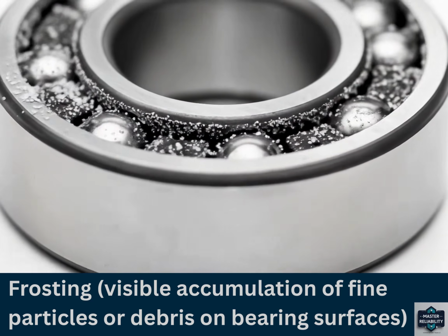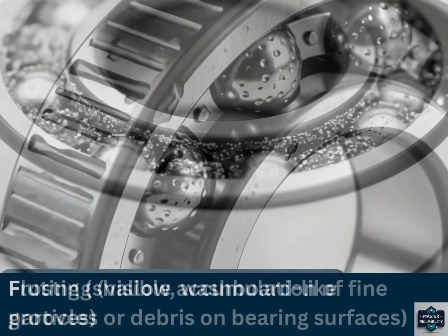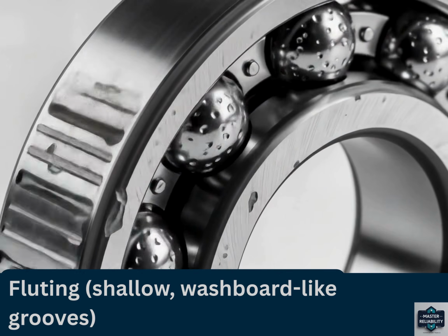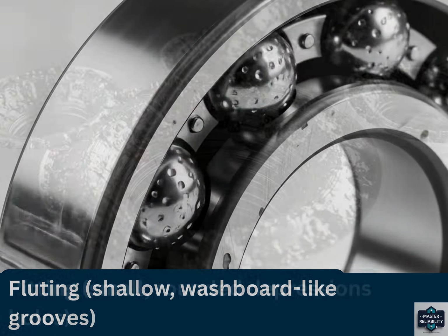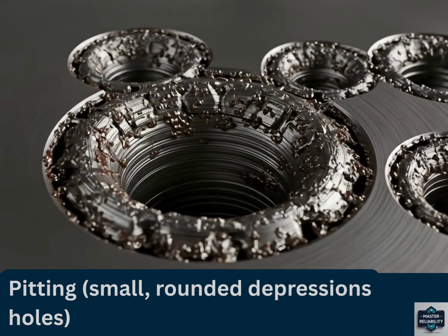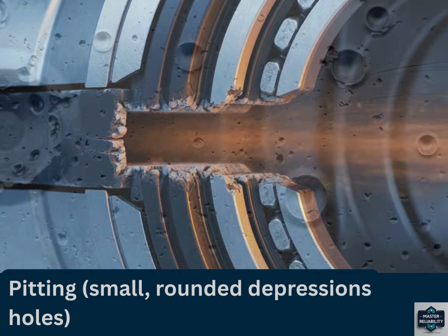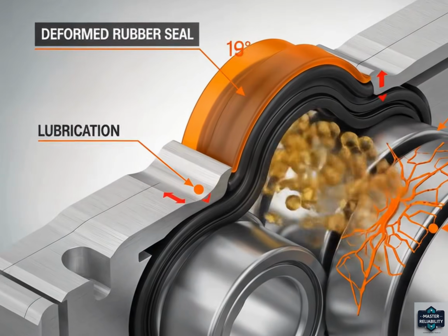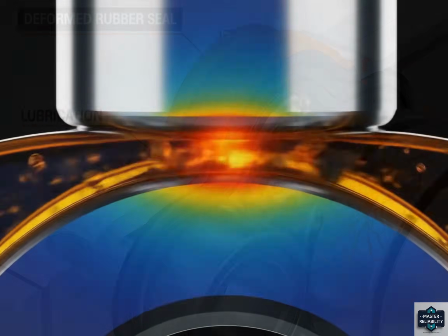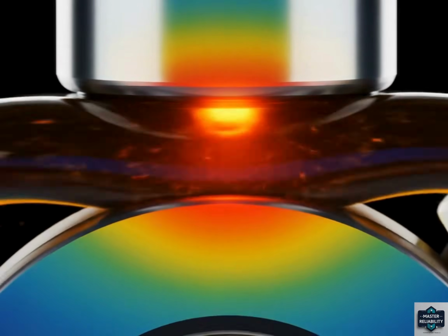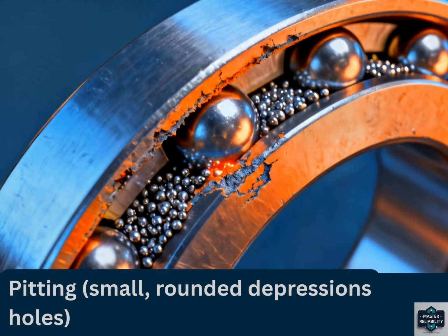of fine metallic debris on the bearing surface, fluting, shallow washboard-like grooves along the raceways, and micro-pitting, small rounded depressions on both the rolling elements and raceways. ESD damage alters surface metallurgy, disrupts lubricant films, accelerates oxidation, and produces hard debris that circulates within the bearing.